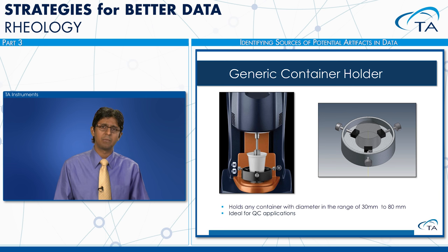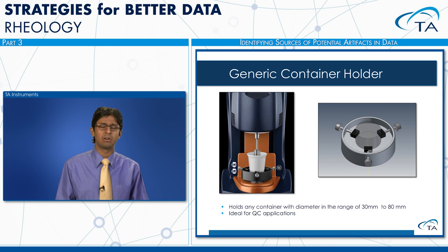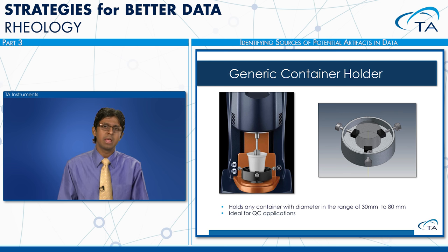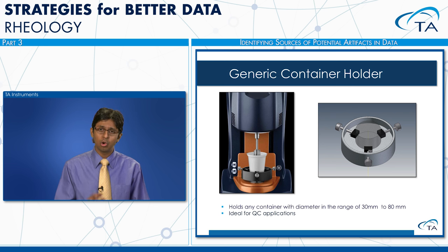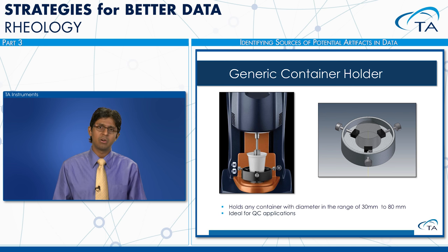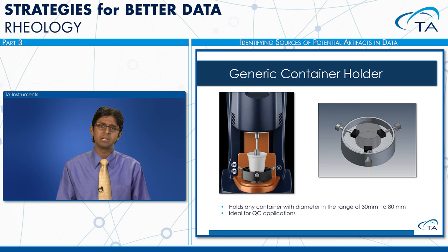For the Peltier plate, a generic container holder — a base platform accommodating any container with diameter between 30 and 80 millimeters — is ideal for testing structured materials like yogurt that cannot be loaded between parallel plates, or for testing paint directly from production-lot cans, making it ideal for QC applications.